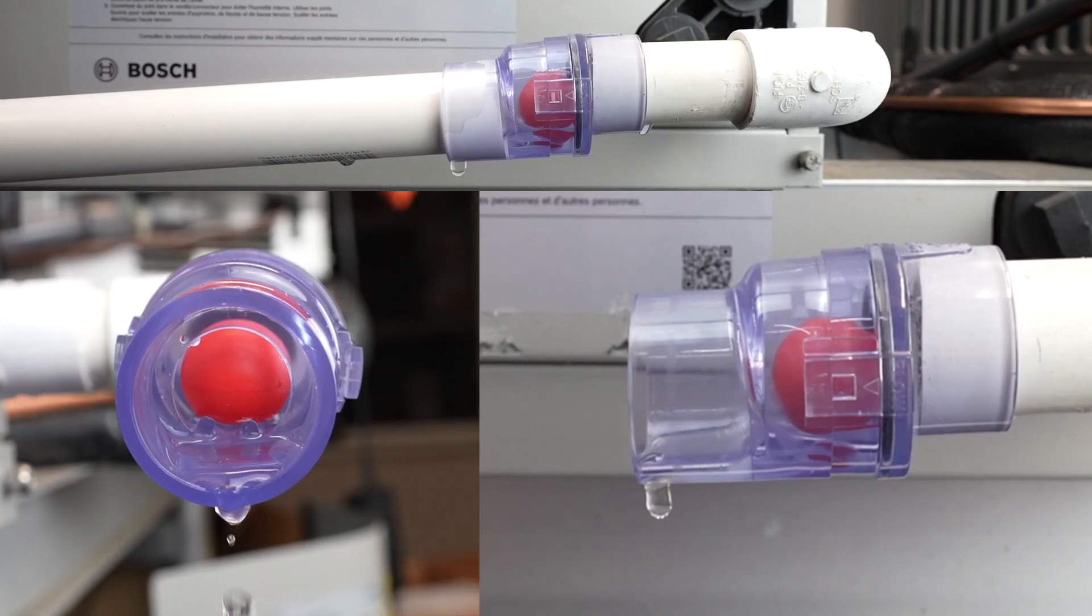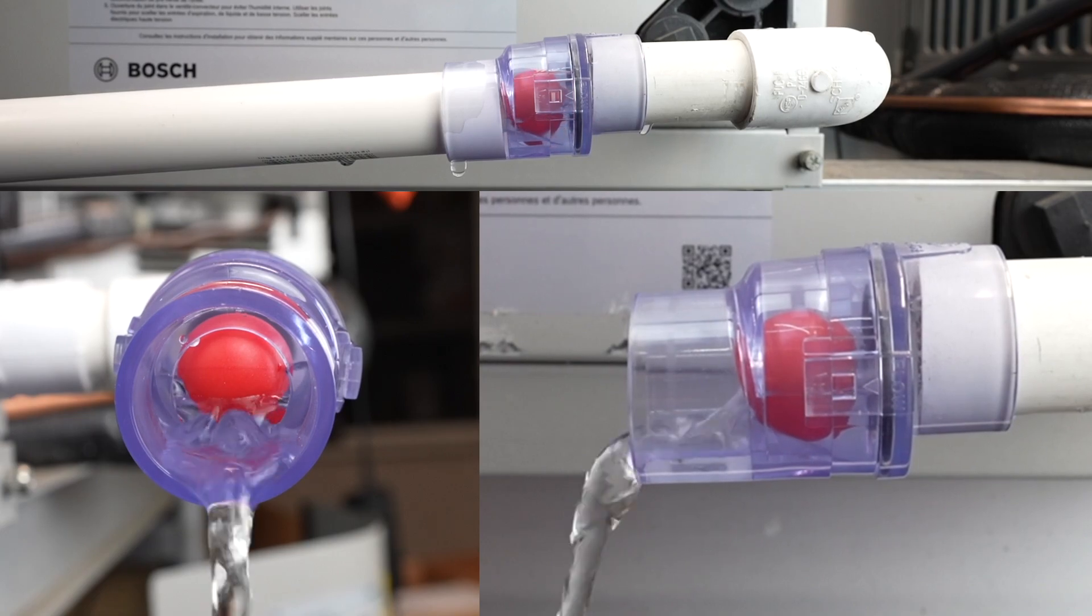The W-Trap was designed for negative pressure systems. When the fan turns on, it pulls the ball valve tight against the 3/8 inch hole, sealing the condensate line.